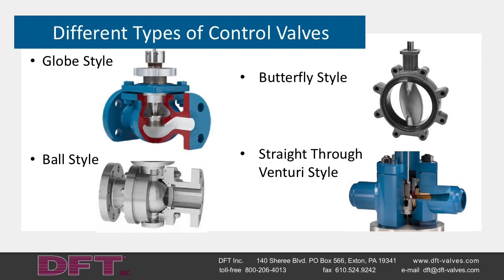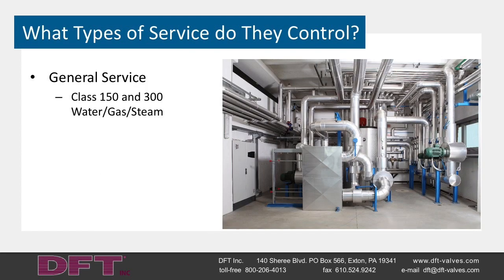Butterfly-style control valves are used in applications that require high CV, high pressure recovery, coarse modulating control, and a range of shutoffs. And finally, there is the straight-through Venturi-style control valve used in applications that require high CV, high pressure recovery, fine modulating control, and tight shutoffs. What types of service do they control? General service includes class 150 and 300, water, gas, and steam service. An example of general service would be 30 PSIG air at ambient temperature in an HVAC system.